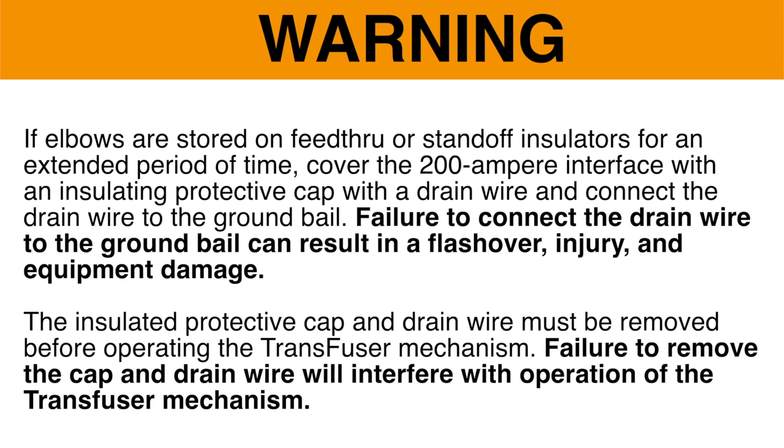If elbows are stored on feed-through or stand-off insulators for an extended period of time, cover the 200-ampere interface with an insulating protective cap with a drain wire, and connect the drain wire to the ground bail. Failure to connect the drain wire to the ground bail can result in a flashover, injury, and equipment damage. The insulated protective cap and drain wire must be removed before operating the transfuser mechanism. Failure to remove the cap and drain wire will interfere with operation of the mechanism.